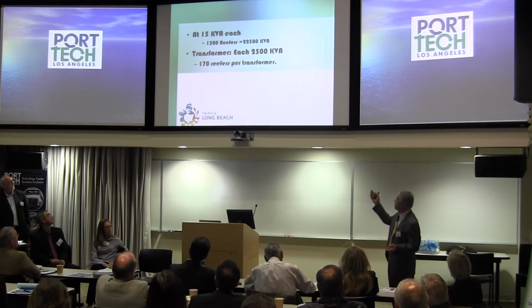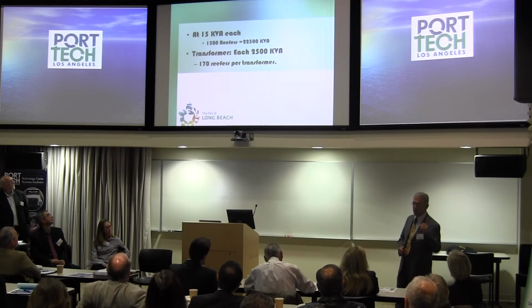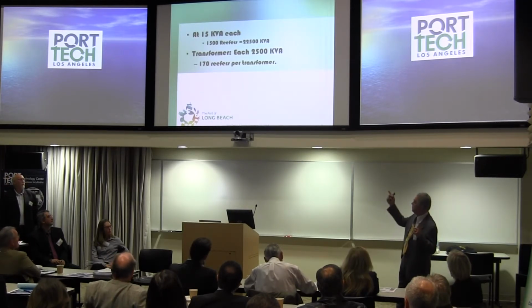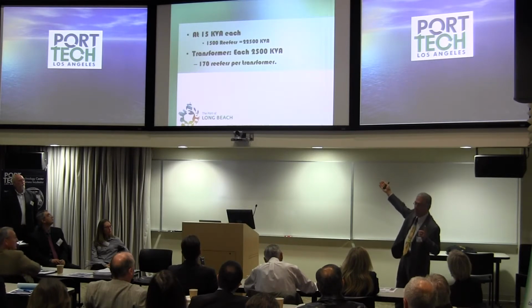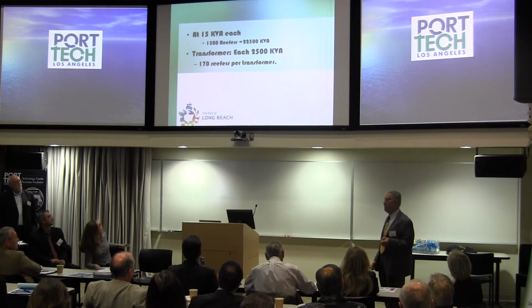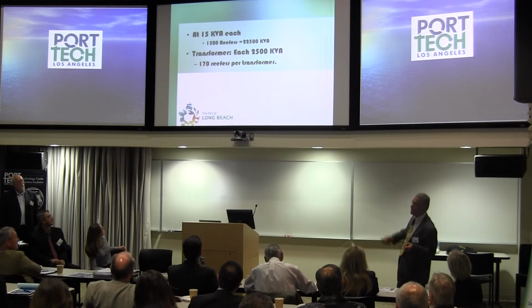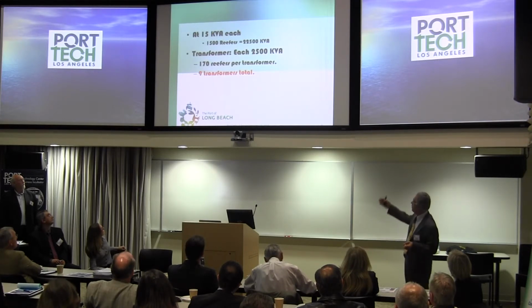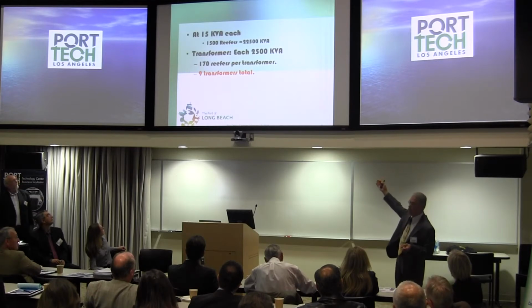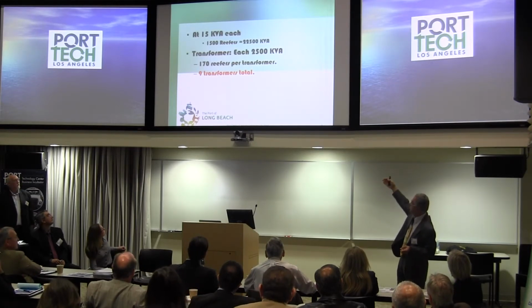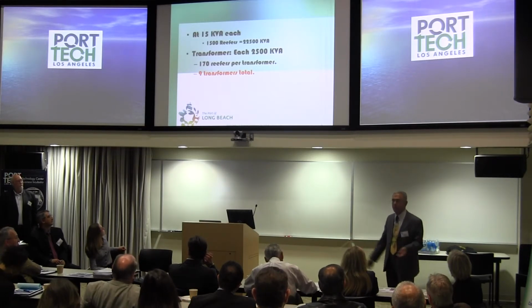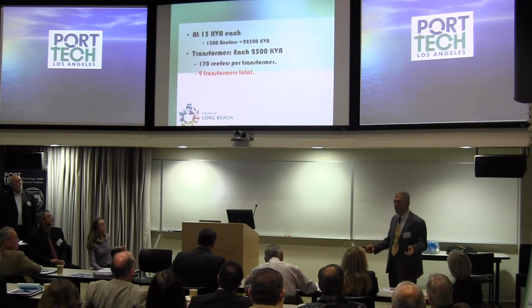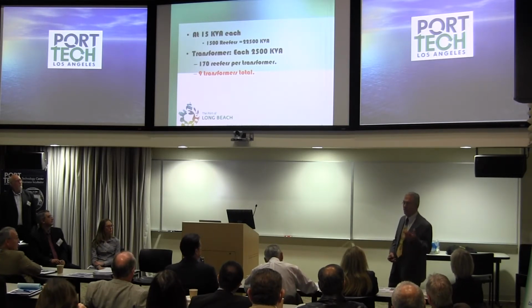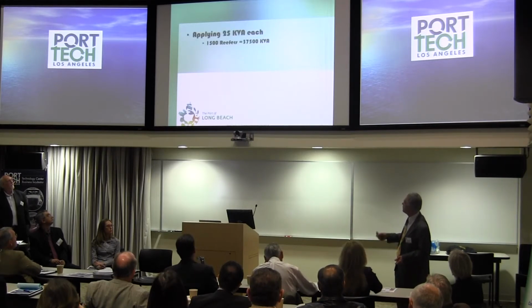It's identical. So now we have a 2,500 kVA transformer that we're going to be using, and each one can handle 170 reefers. It's a very simple math. You multiply 170 by 15, that's 2,500. And that's how many reefers that particular transformer can supply. Now, if you're using 2,500 and you have 22,500 kVA total load, you divide one into the other and you end up with 9 transformers. That's really as simple as it is. It doesn't take a lot of genius to try and figure these things out. But you have to start, remember, from 15 kVA. That's the start. So with 15 kVA, you use 9 transformers.